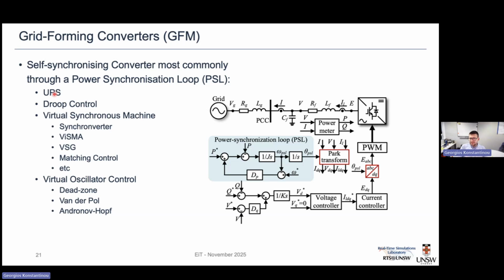But when this happens within a network, we need to see how we can better share this power with everything else that exists in the network, which means we need to start looking at introducing things like droop control that allows us to do some power sharing between the converters, or replicating some of the responses of synchronous machines within the control structure of the power electronic converter.